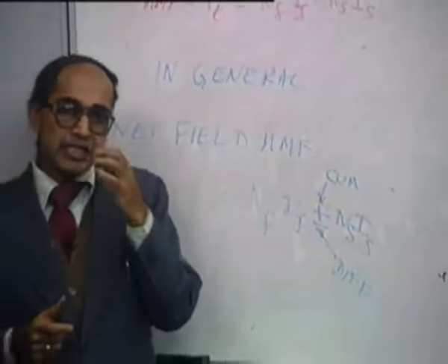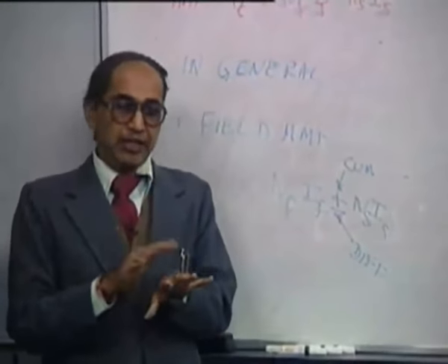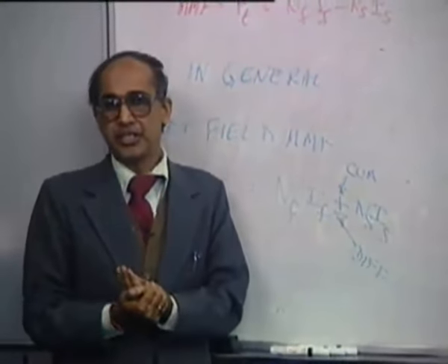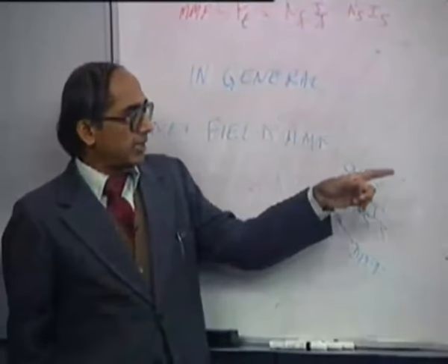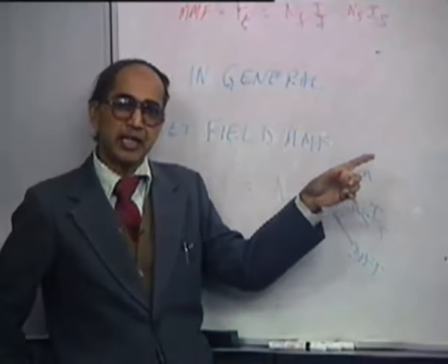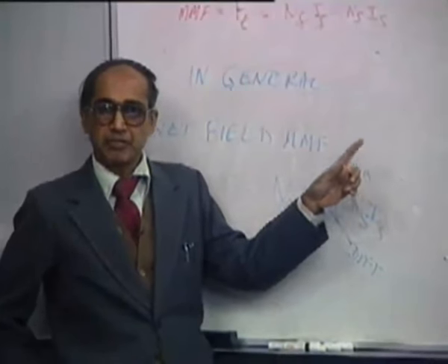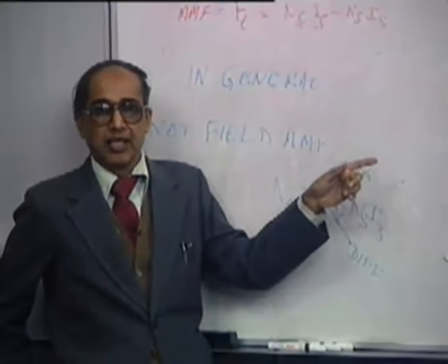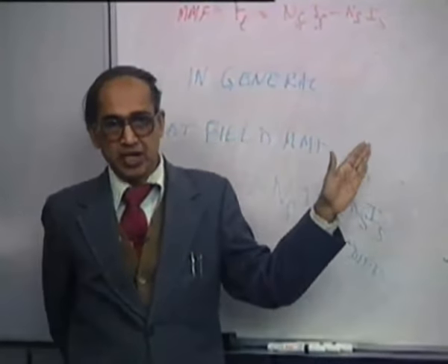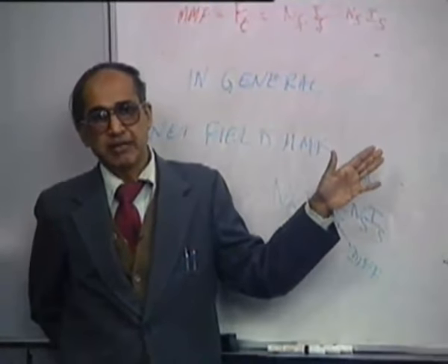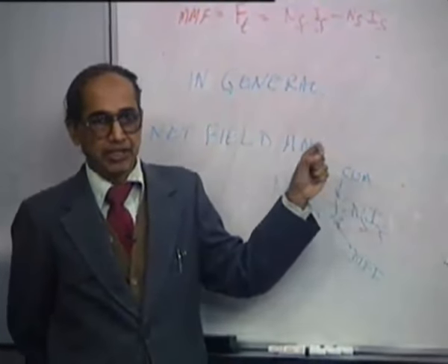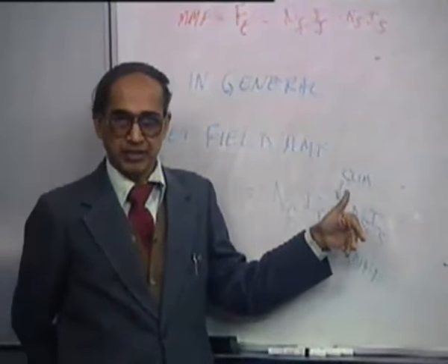the important thing is, how do you identify them? What are the different design changes in the two windings? We must understand that the shunt field must carry the nominal voltage but smaller current, and it must have less losses, which means it must have high resistance, made of thinner wires, more number of turns.